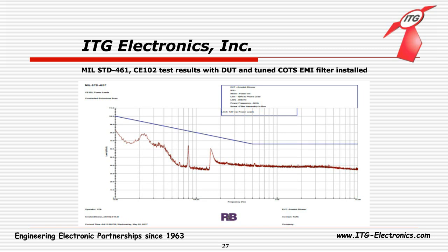Right, and I suppose if the filter is symmetrical, then it certainly doesn't matter which way you put it in. But that is correct. I've seen many filters that are not symmetrical, as you're mentioning, where a differential mode capacitor is on one end, and that may not work the other direction. Okay, thank you. That's very true.